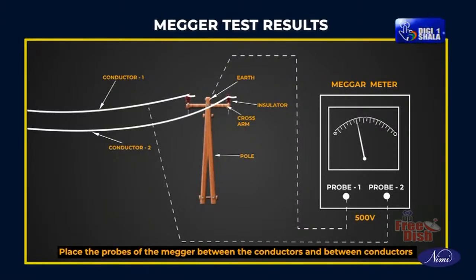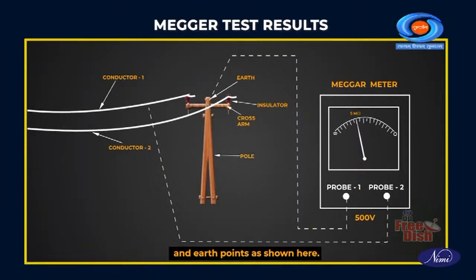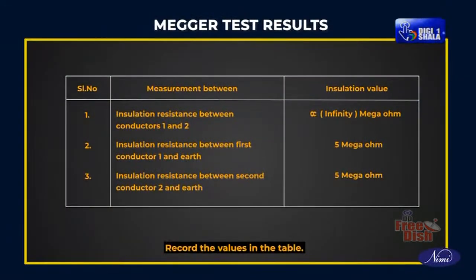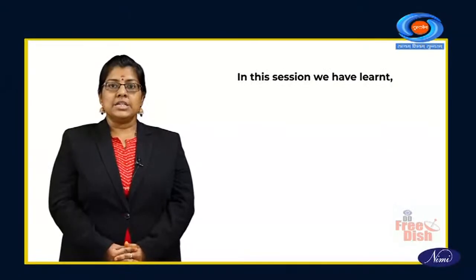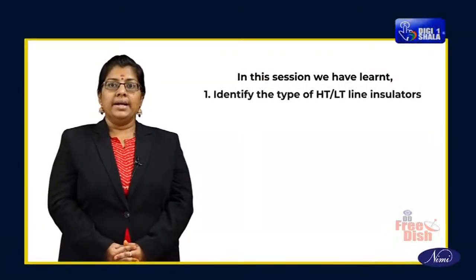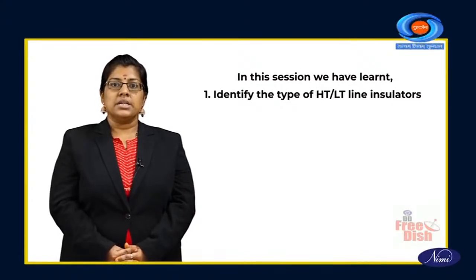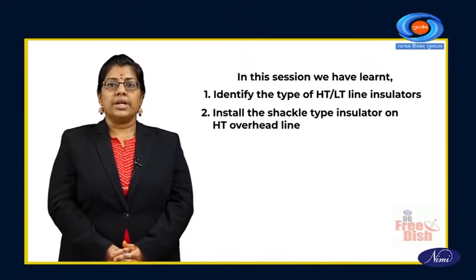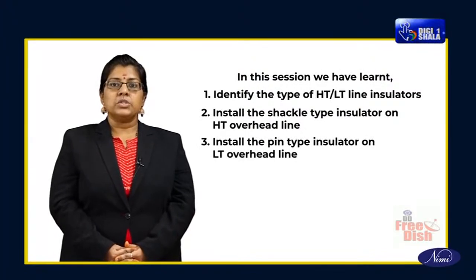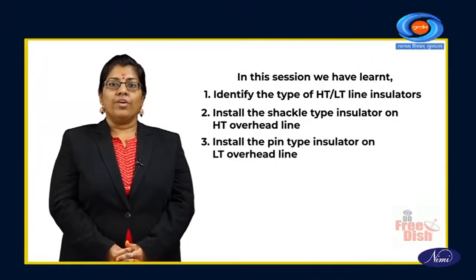Place the probes of the megger between the conductors and between conductors and earth points as shown here, and measure the values. Record the values in the table. Recap. In this session, we have learnt how to identify the type of HT, LT line insulators. Install the shackle type insulator on HT overhead line. Install the pin type insulator on LT overhead line.